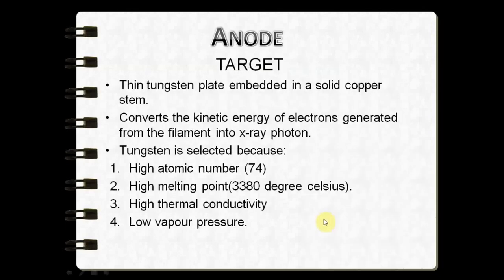The positively charged anode contains a thin tungsten plate embedded within a solid copper stem. Tungsten is the material of choice because it has a higher atomic number of 74, indicating a high charge on the nucleus, more protons, and higher binding energy of the orbital electrons. This gives rise to increased interaction between electrons and atoms, thereby increasing x-ray photon production.